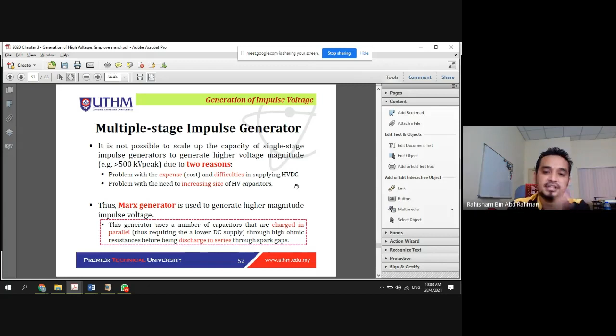So why go for the multiple stage impulse generator? Because we don't want to spend money on a higher voltage rating for a single impulse unit. Also, as mentioned previously, there's the problem of increasing the size of the lab - for example, the clearance, and for equipment like the HV capacitor, we'd need a very big one with a very big rating to develop the very high magnitude.